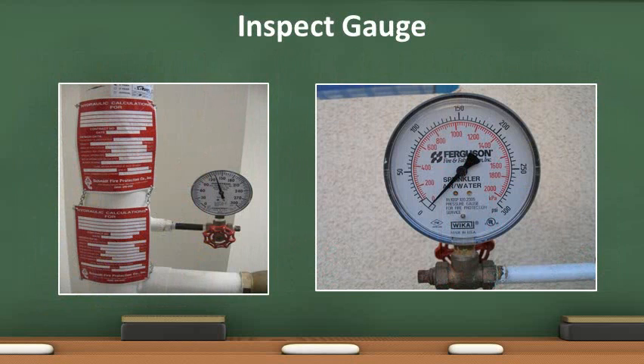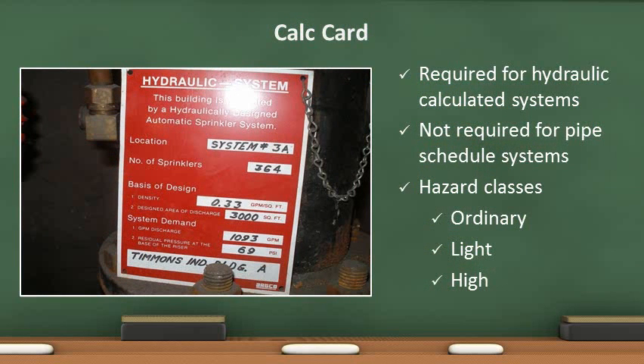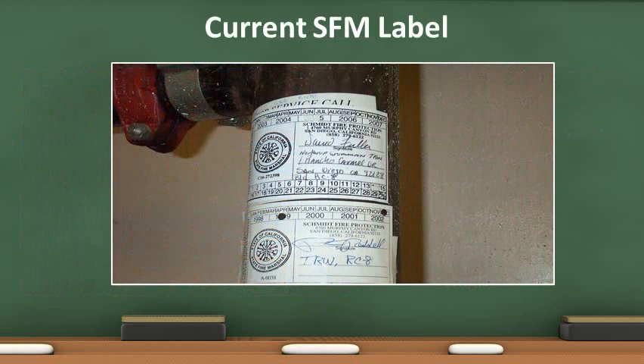Visually inspect the gauges. They should be in good condition and readable. Check the pressure and compare it to the calculation card. In the photo on the left, there is no pressure indicated on the gauge. In the photo on the right, there is pressure in the system. Hydraulic nameplates for hydraulically designed systems shall be inspected quarterly to verify that it is attached securely to the sprinkler riser and is legible. Labels indicating the five-year certification date shall be used on water-based fire protection systems and shall be securely attached to each automatic fire extinguishing system at the time of service.